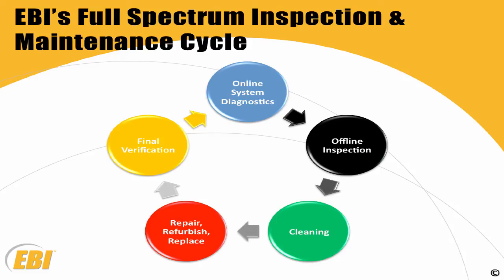Then you need to clean the bus. Then you need to go in and repair or refurbish everything that you find during the offline inspection. Then you need to have a final verification, which would be a high pot test, before you go back online. Then you come back around and you can do an EMI test again, and you have a baseline from the first one to know the progress you made during the actual inspection.